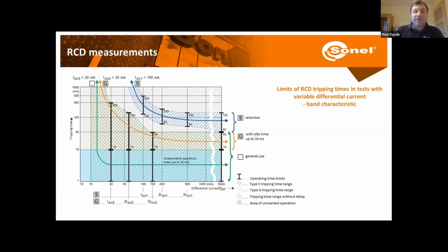But if we would like to use this RCD as a short delay one, then we need to look at the orange field on the graph over here. So for the nominal current, 30 milliamps, it will trip from 10 milliseconds up to 300 milliseconds. And we can see that there's the border over here. The tripping time starts from 10 milliseconds. And similarly, in case we would like to use it as a selective one, then we look at the blue field over here.